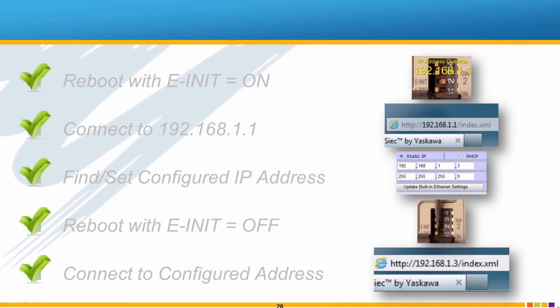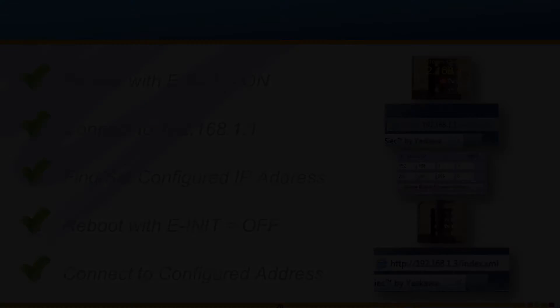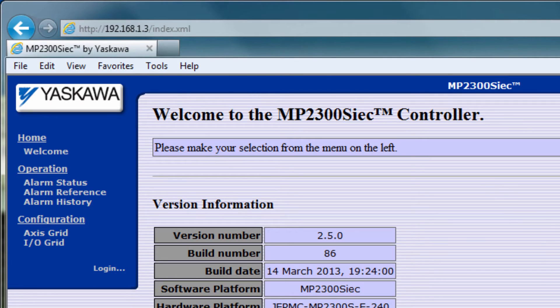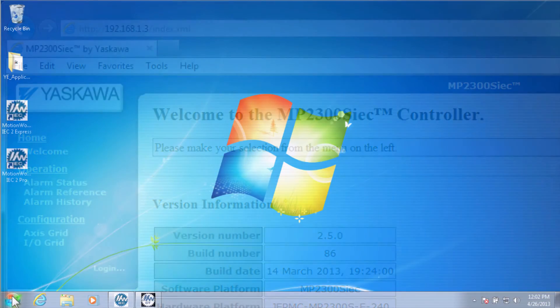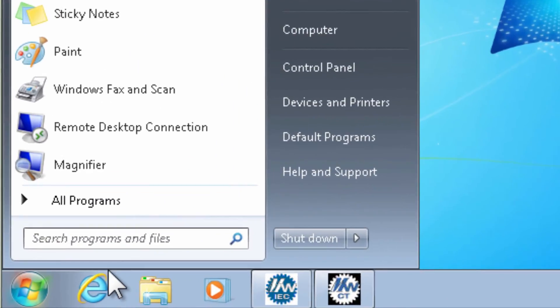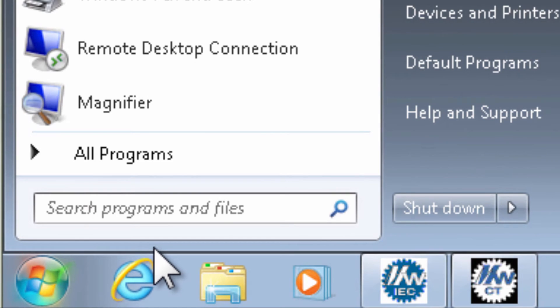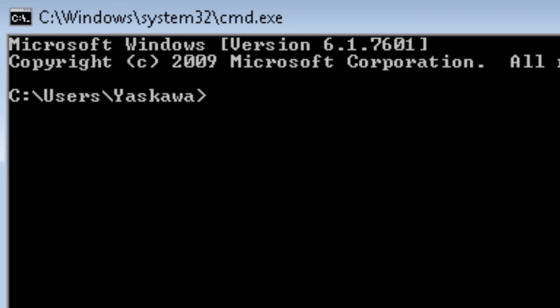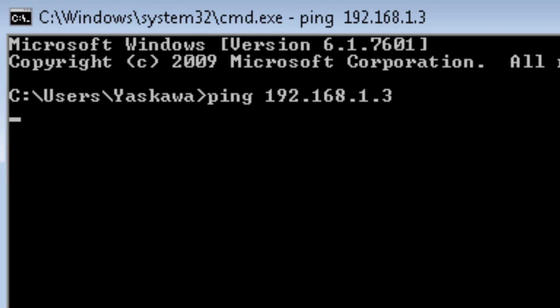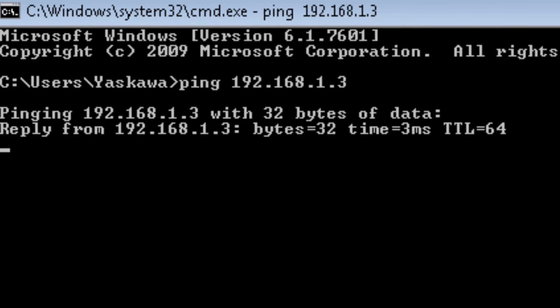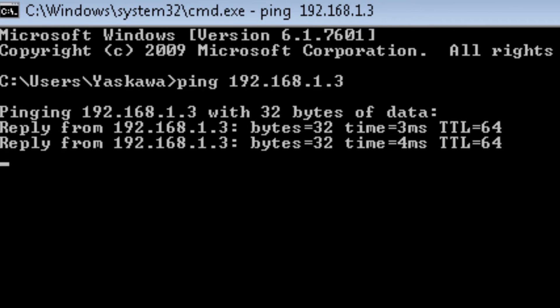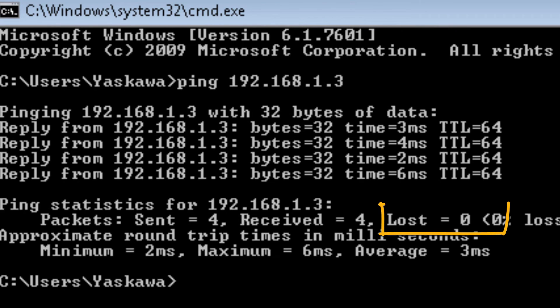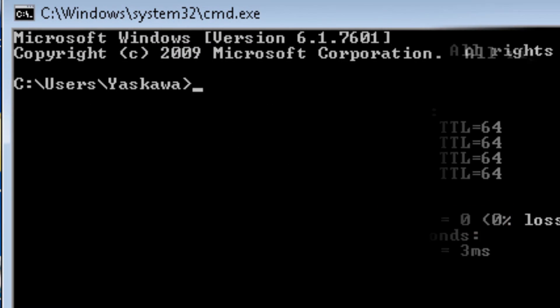If for some reason you cannot connect to the controller, a ping test is a basic troubleshooting operation. To do the ping test, under the start button, type cmd, then type ping followed by the IP address of the controller. In this example 192.168.1.3. You want the result to be 0% loss. If the request shows timed out or shows loss, then this confirms that you have a connection problem.